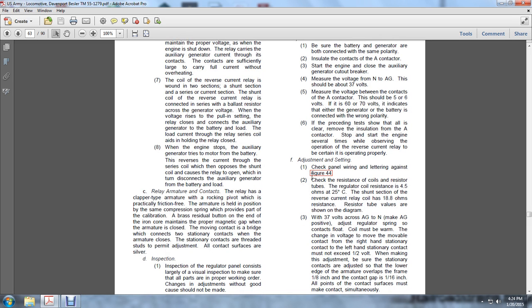When the engine stops, the auxiliary generator tries to motor from the battery. This reverse current through the series coils will oppose the shunt coil, causing the relay to open, which in turn disconnects the auxiliary generator from the battery load. C. A relay armature contact.